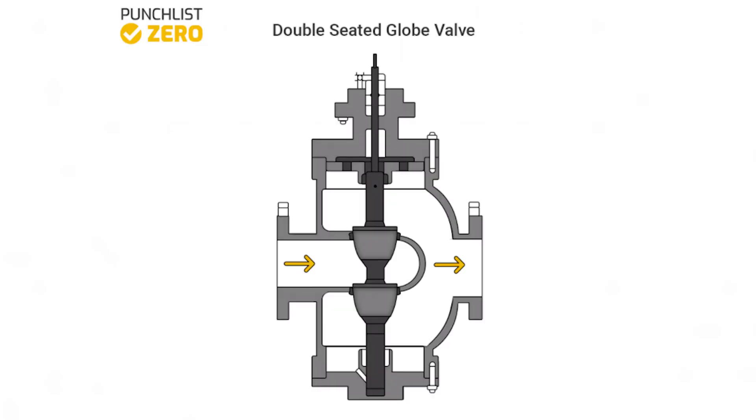The typical globe valve design consists of a single seat with a disc that moves in and out of the flow path. A double seated design with two plugs also exists. This two-plug design cuts the hydraulic load on each disc in half.